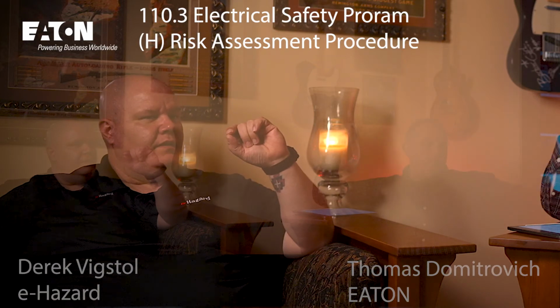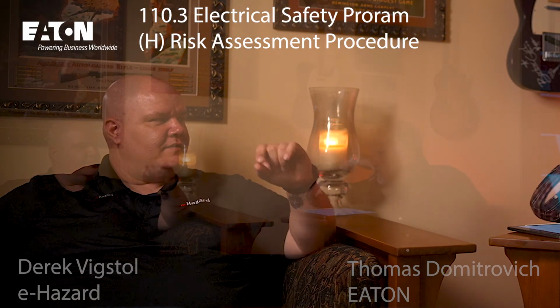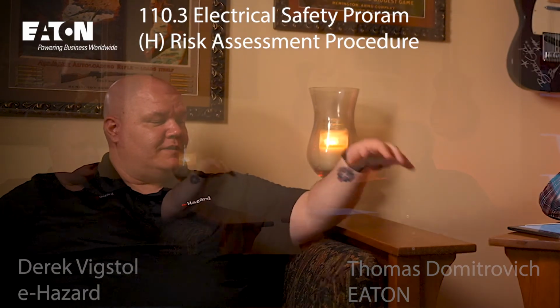But it often gets missed, again, remember, there's risk assessment from the employer standpoint. There's risk assessment from the worker standpoint. And the stuff that we can do ahead of time, the incident energy estimates, the voltage estimates, the boundaries, like we figure out what our shock boundaries are and arc flash boundaries, we can do all that stuff ahead of time. But when we go to actually do the work, there's a whole lot of gaps we got to fill in. So what am I doing? How close am I getting to the equipment? What kind of, again, details?